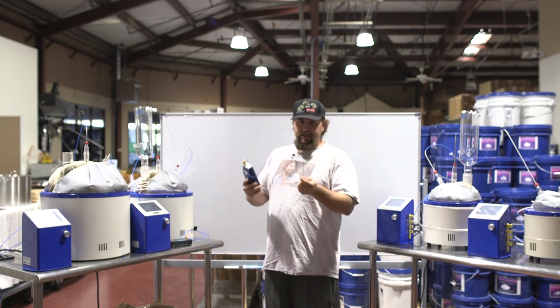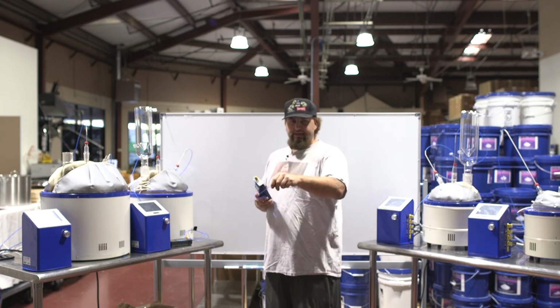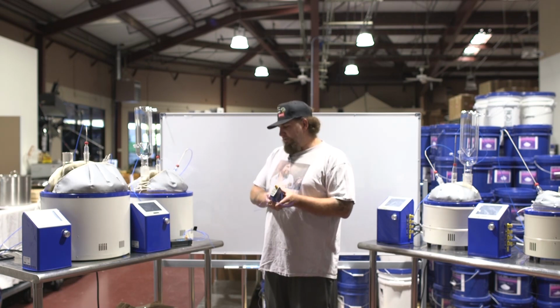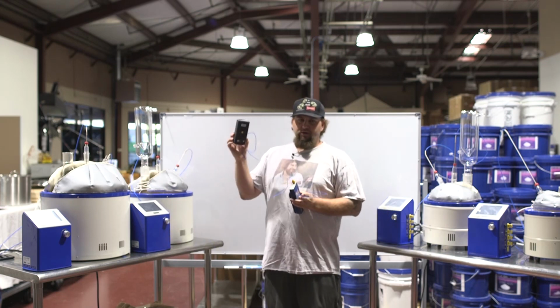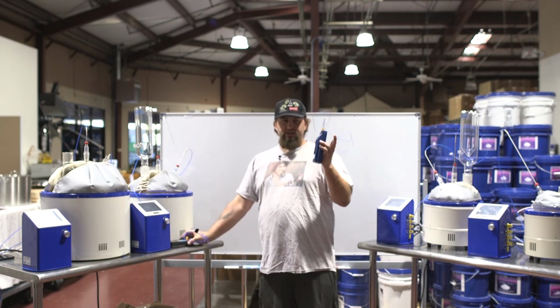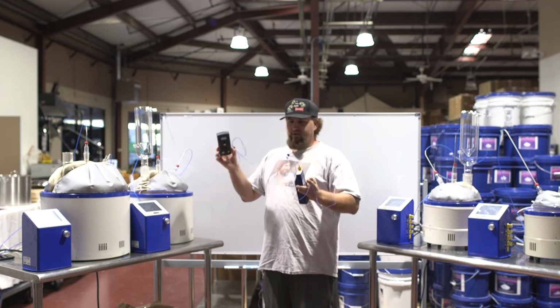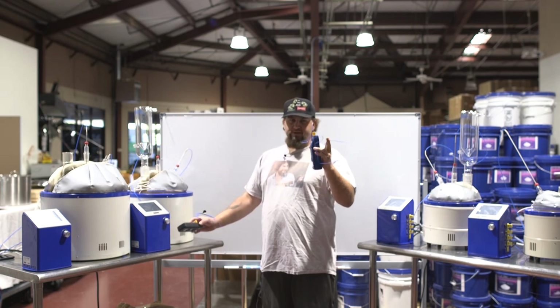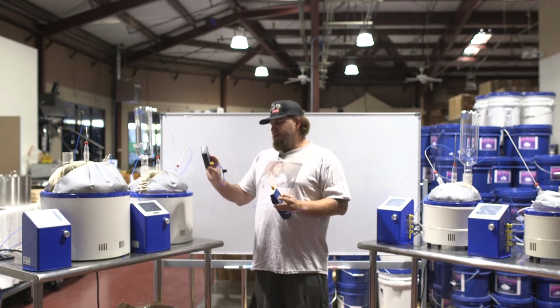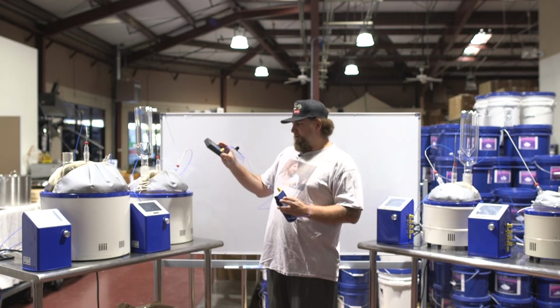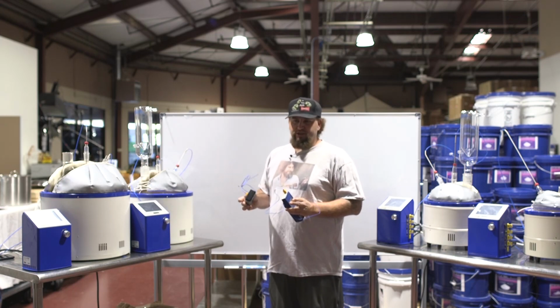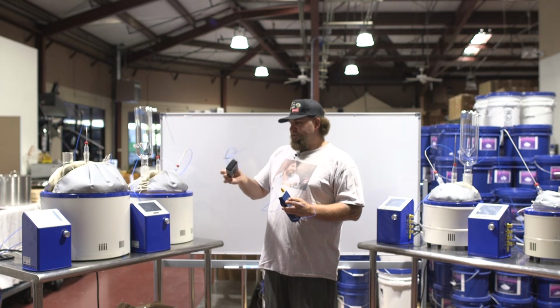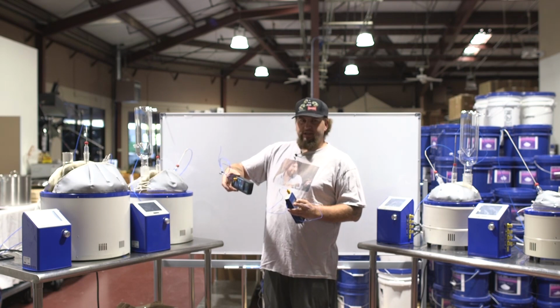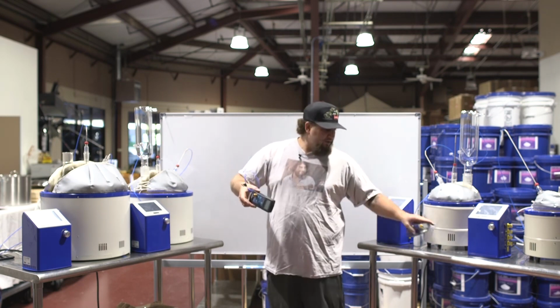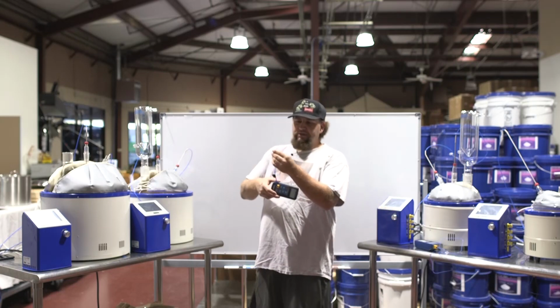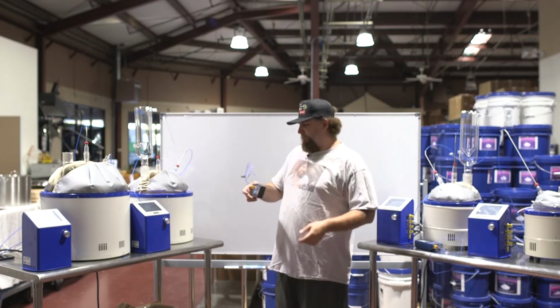So I'll generally take this calibrated unit and put it in something that's hot, and once it's stable, I'll throw this guy in there and I'll run this on a daily basis. And I use this just to calibrate against, so I have an actual standard, but I don't wreck this thermometer. So that's why I use this unit on an everyday practice, and usually as customers purchase mantles from us daily, this thermometer itself is like $15.99 up here, and it will last for about a month of everyday use before that tip just breaks apart.